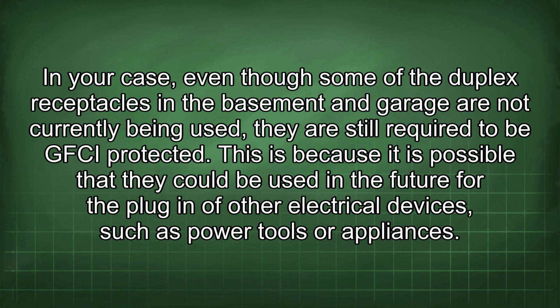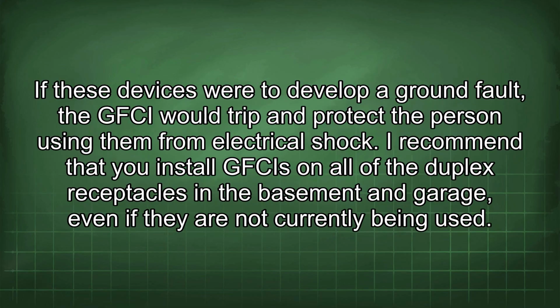In your case, even though some of the duplex receptacles in the basement and garage are not currently being used, they are still required to be GFCI protected. This is because it is possible that they could be used in the future for the plug-in of other electrical devices, such as power tools or appliances.